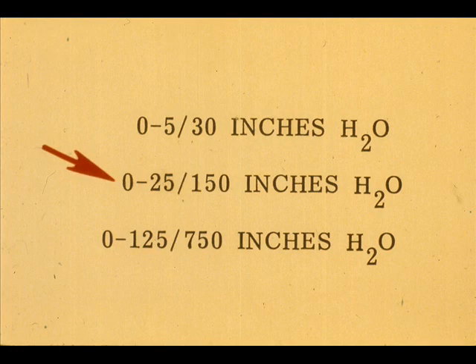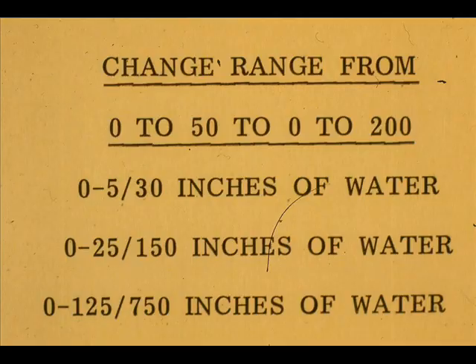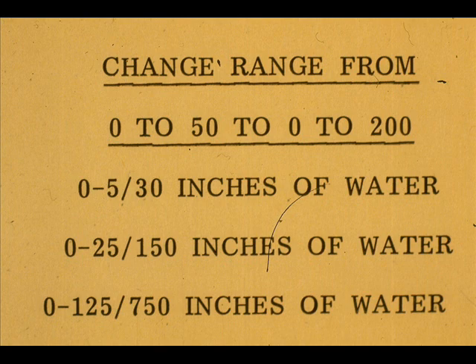For example, take the 0–25/150 inches of water sensor module: the minimum span is 0 to 25 inches of water, and the maximum span is 6 times 25, or 150 inches of water. A range change from 0–50 to 0–200 inches of water would require the sensor module to be changed.